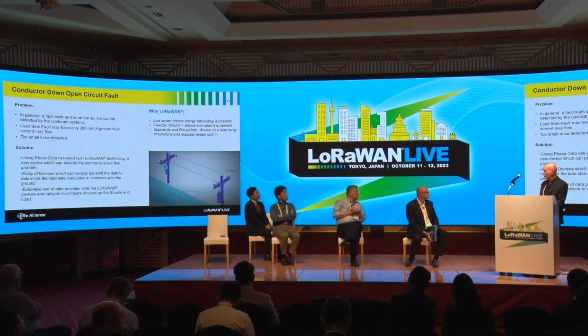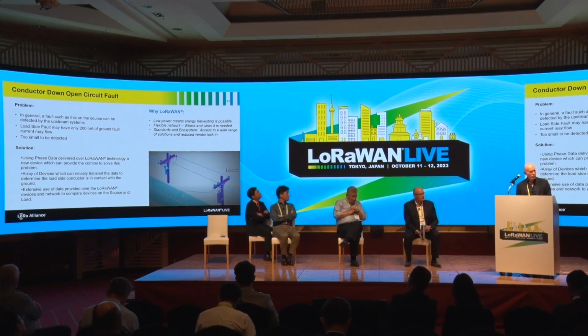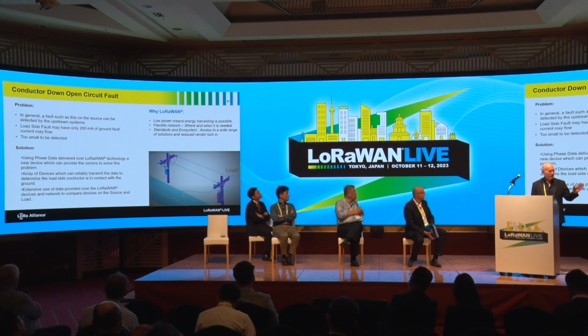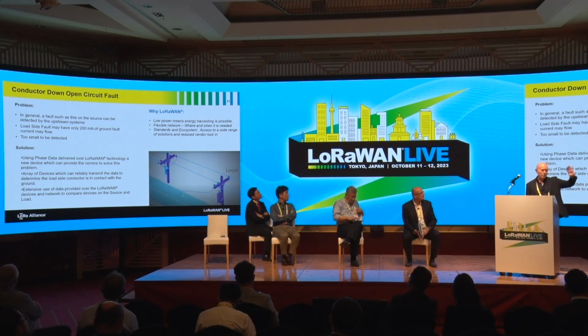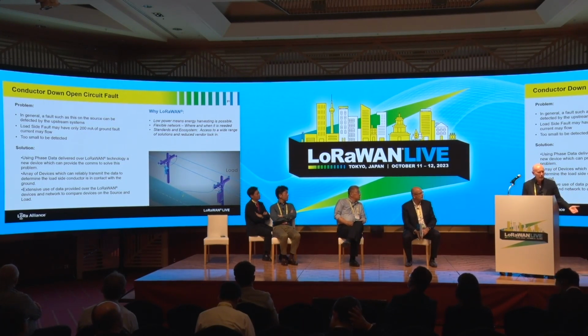Incredibly powerful solution. This other one here, this is a really super important issue for any power utility, and it's this conductor down problem. I don't know if anyone here is from the power utility space or has much exposure or experience in it, but just a very quick problem statement. In all transmission networks, the upstream transformers have a lot of power traversing through them, and while they're live, there's a lot of information being gathered to the back at the head end system. If you get a conductor down at the upstream transformer end, you'll get a high current flow to the ground.